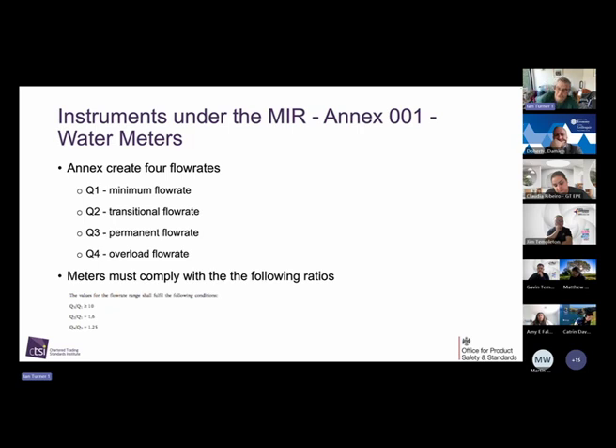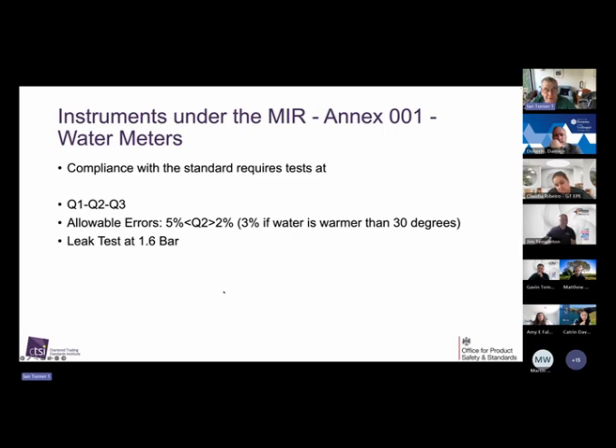And the way it works, and you can see at the bottom of this slide, you've got ratios. So when you start looking at it, it's all connected to flow diagrams and things like that. And they have something called a turn down ratio. So the higher the turn down, the lower the turn down ratio, the smaller these ratios, the more accurate your meter. So compliance with the standard requires tests at 1, 2 and 3, and there's your allowable errors, so 5% to 2%. And there you see we've got the gap 3% if it's warmer. So if you've got a warm water meter rather than a cold water meter, and you have a leak test at 1.6 bar.